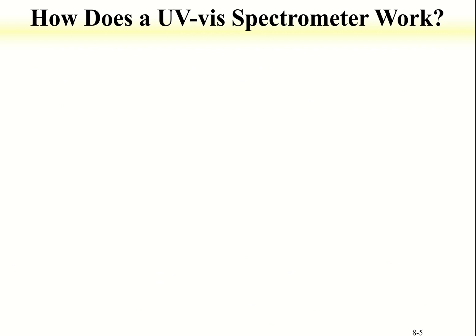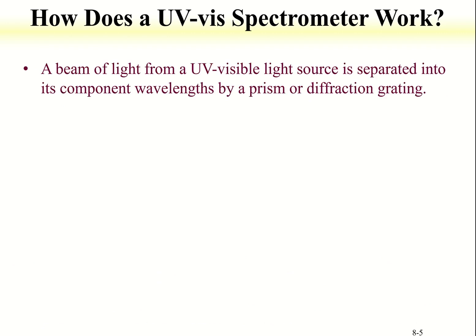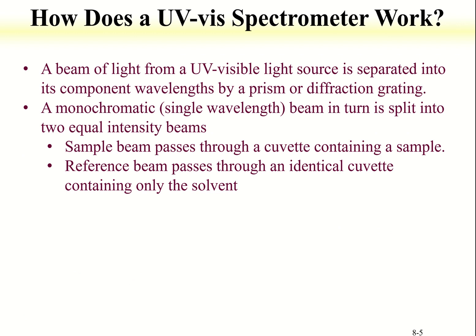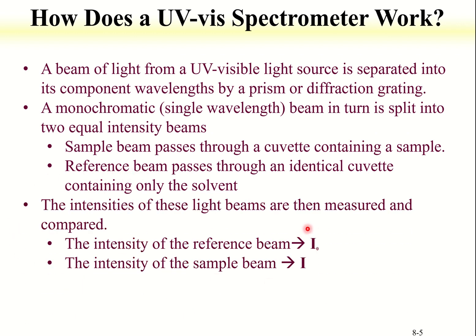In a UV spectrometer, a beam of visible light source is separated into its component wavelengths by a prism or diffraction grating. The monochromatic beam is then split into two beams of equal intensity. One beam is to pass through the cuvette which contains a sample. The other beam is to pass through another cuvette which contains only the solvent. The intensities of sample beam and reference beam are then measured and compared.